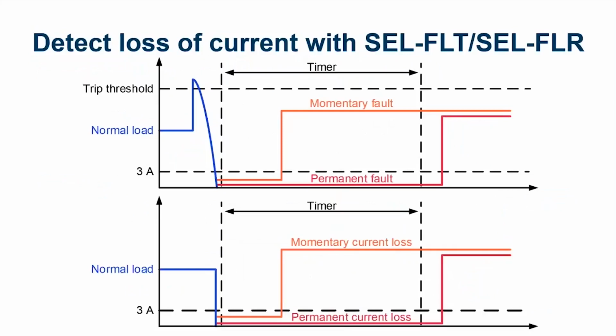So we can distinguish between a permanent and momentary outage fault, and we can also look at a momentary and permanent loss of current. In this case, if we're armed and have normal loading and then suddenly our current drops below this 3 amp threshold, then we have a timer that is set to see whether that is a permanent or a momentary loss of current. This is a user settable timer. Once that expires, if the current has come back, then this was a momentary loss of current, or if the current has still not returned, then it's a permanent loss of current. So we can use that loss of current indication, especially comparing to our other phases, to say that we potentially have an open phase condition.